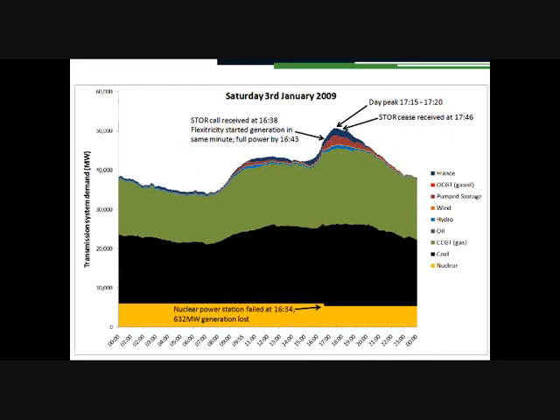Here is one particular event from a number of years ago — a fairly typical event for us. From midnight to midnight, you can see electricity consumption provided through nuclear, coal, and gas in different colours. At 34 minutes past four in the afternoon, a nuclear power station failed — just before the evening peak — putting the system into crisis. Within four minutes we received an instruction from National Grid control to start generation and turn down consumption. Within five minutes we were at full power on various sites. National Grid held us in that mode for just over an hour before we received the cease, carrying the system through the evening peak. This is what is called a Short Term Operating Reserve call — a STOR call.